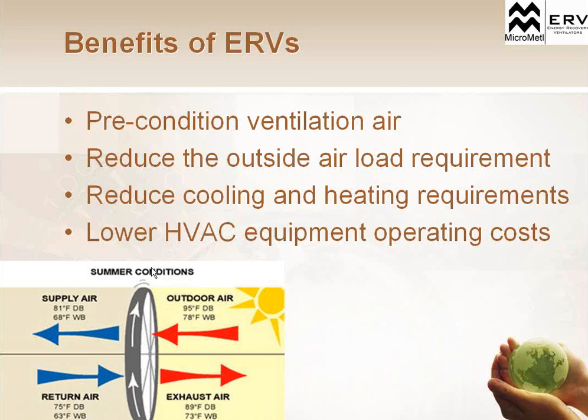What happens is we take that return air in the summer. This is a summer example here. Let's say we have 75 degrees in our building. We take that energy, we pass it over this wheel. This wheel is actually spinning between both airflows. So we have our exhaust airflow here. We've got our supply airflow here. So this energy travels on the wheel to the other airflow where we're bringing in hot, humid outside air, 95 degrees. We're bringing in fresh outside air, which just happens to be 95 degrees. It picks up the energy on the wheel, lowering the sensible energy and the latent energy, essentially cooling the outside air and dehumidifying it. And then we get 81 degree supply air. So normally if we were bringing in straight outside air from an economizer, our rooftop would be seeing 95 degrees. Well, now we've pre-cooled that to 81 degrees just by use of a mechanical transfer wheel.